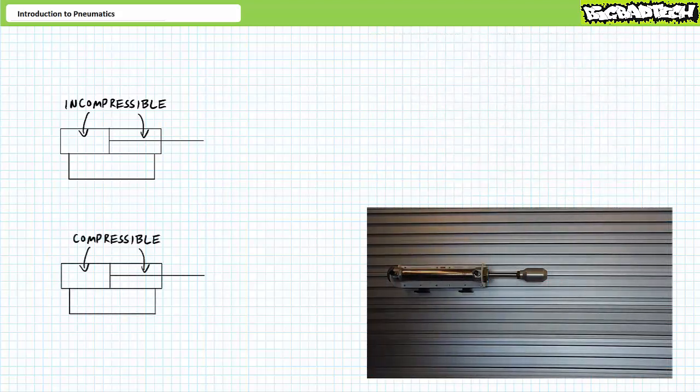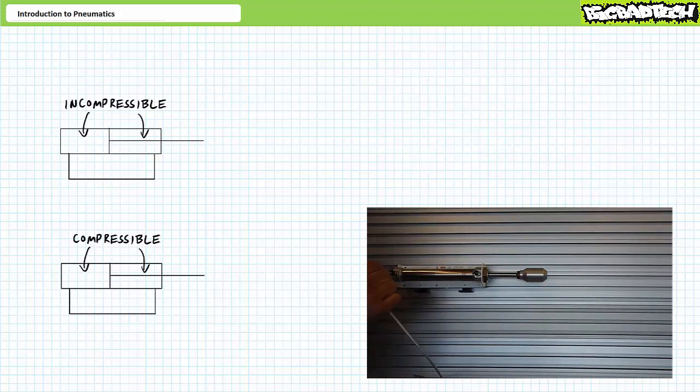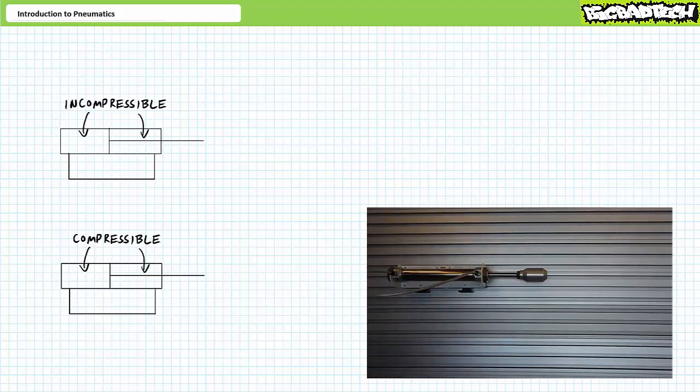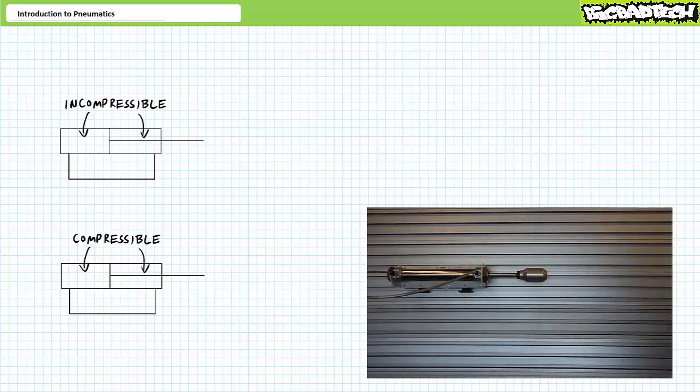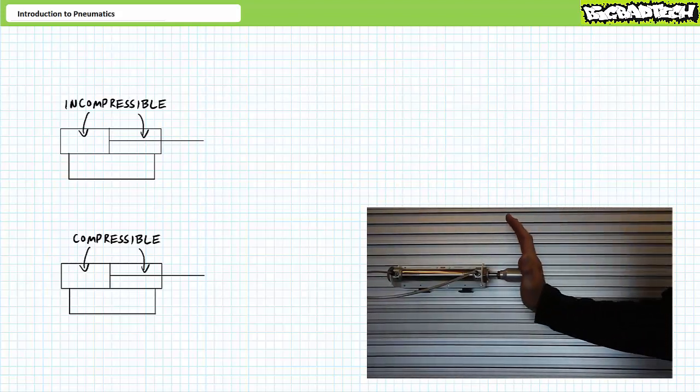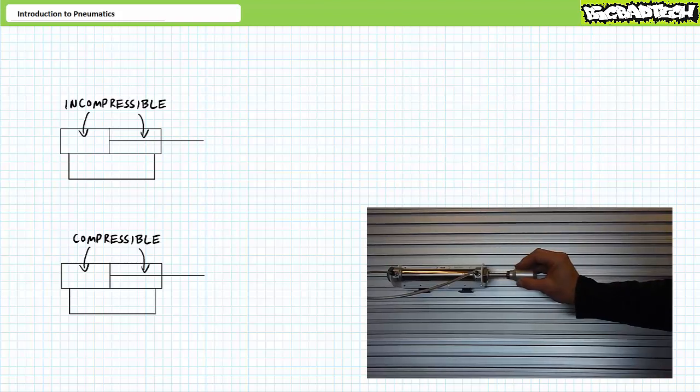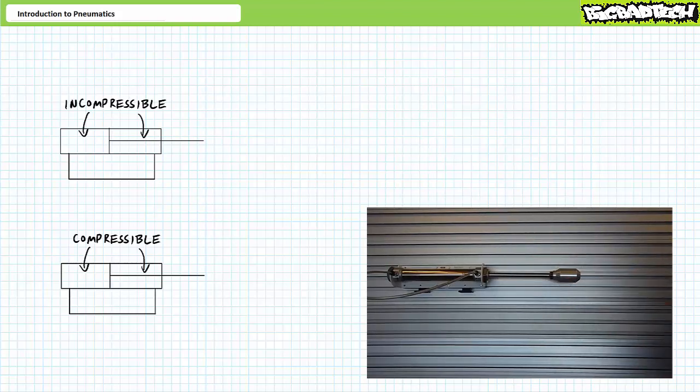Not so with a pneumatic cylinder. Consider partially extended double-acting pneumatic cylinder with a rod end and cap end joined together at atmospheric pressure. Can an external force push the rod back in? No problem. The larger volume of the air in the cap end compresses into the smaller end with relative ease. Can an external force pull the rod out? Not an issue. The smaller volume of air in the rod end expands into the larger cap end with relative ease.